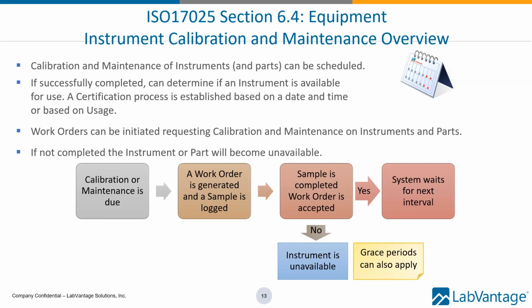When it's successfully completed, the equipment is available until the next time that it's due. If it's not completed, the instrument could be automatically taken offline. You could even set some wiggle room in by using a grace period. Even when doing daily performance checks, if an instrument does not pass specifications, it can be taken offline to mitigate analysts inadvertently assigning that equipment to a batch of samples, which helps to avoid corrective actions or even the need to correct paperwork.